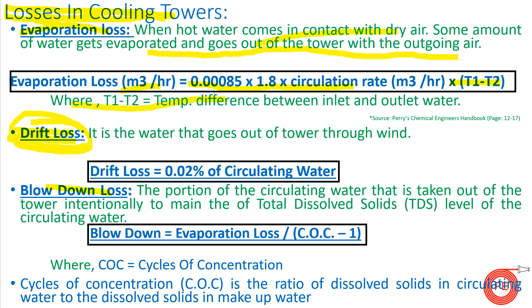Drift loss is a very minor loss — it is the water that goes out of the tower through wind, and drift eliminators are used to reduce it. Drift loss is given by 0.02% of your circulating water. Blowdown loss is the next and most important loss: when water continuously evaporates, the total dissolved solids (TDS) remaining in the water increase, which can cause problems in the process and choke tubes, so we must maintain TDS levels.